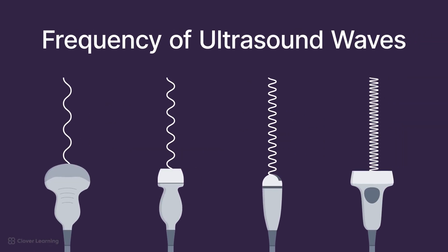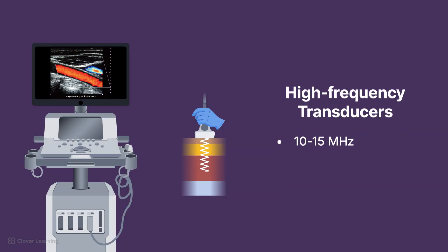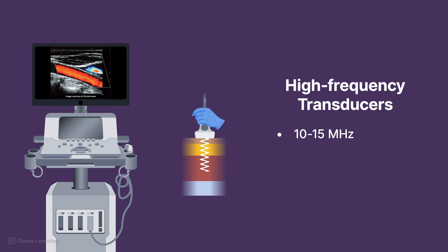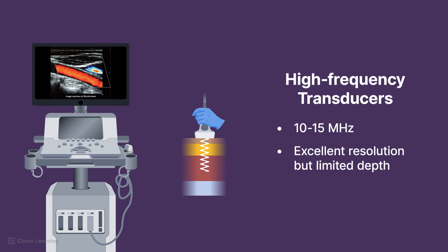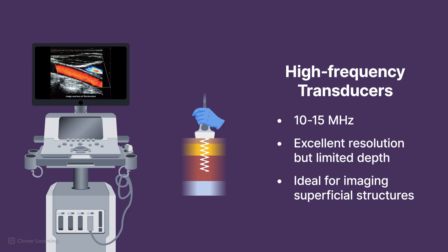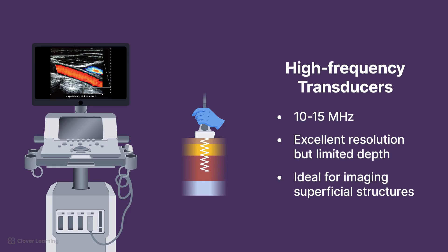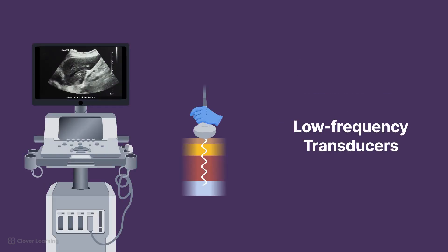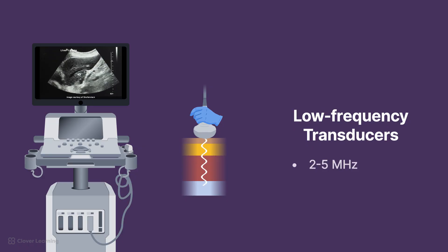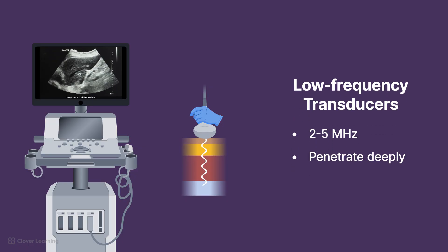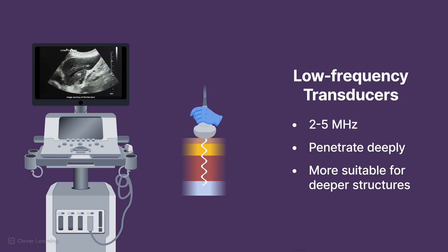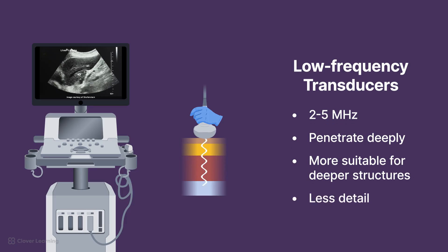It's also important to understand how the frequency of the ultrasound waves affects image quality and depth. High-frequency transducers, such as 10 to 15 MHz, produce images with excellent resolution but are limited in how deeply the sound waves can penetrate. These are ideal for superficial structures like the thyroid, breast, or musculoskeletal tissues. Low-frequency transducers, such as 2 to 5 MHz, penetrate more deeply, making them suitable for deeper structures like the liver, kidneys, or fetus in later stages of pregnancy, though with less detail.